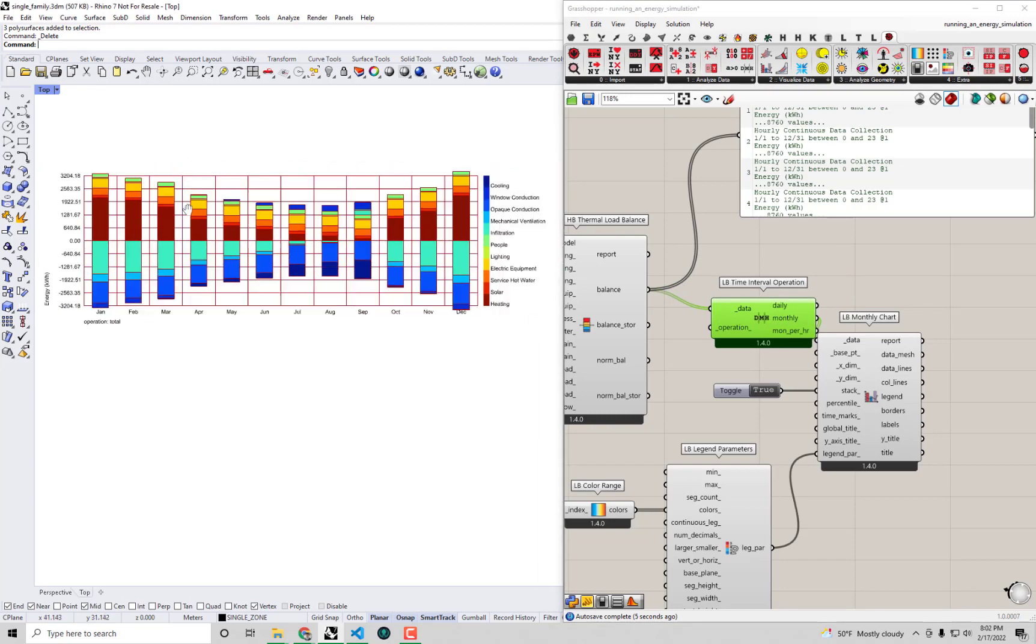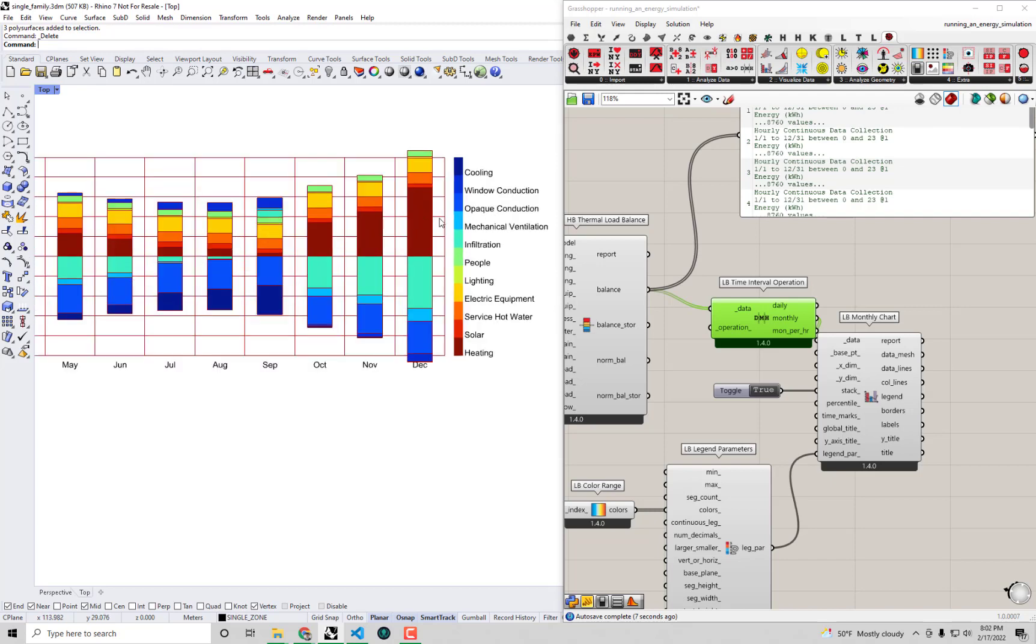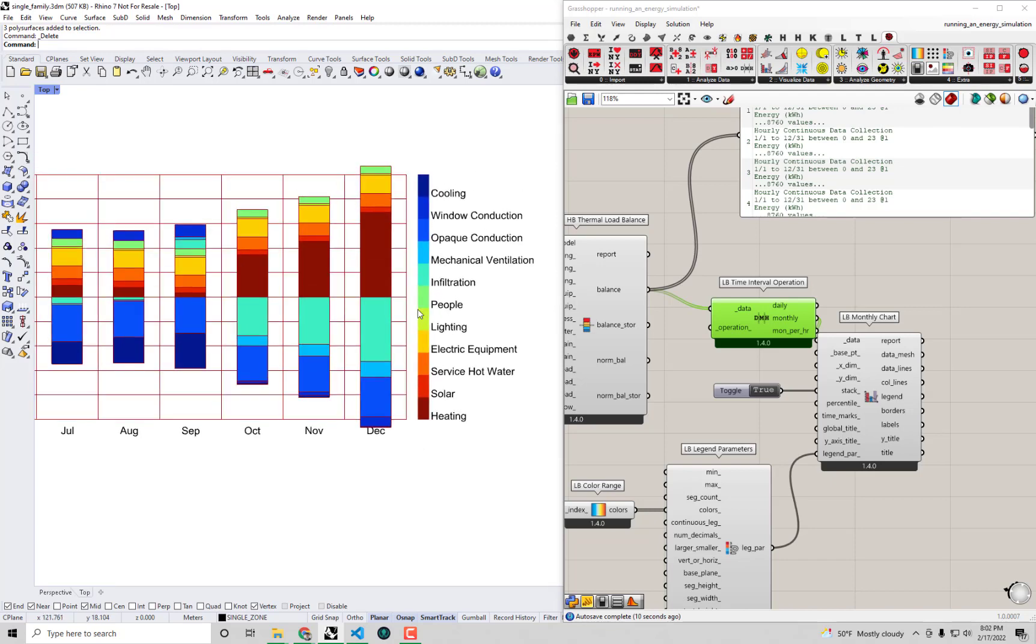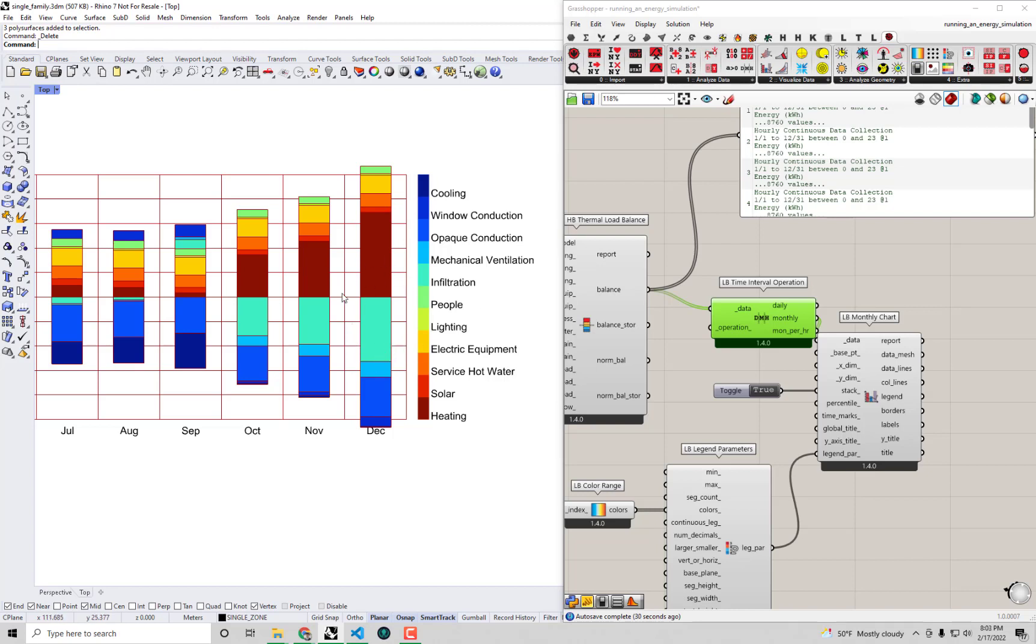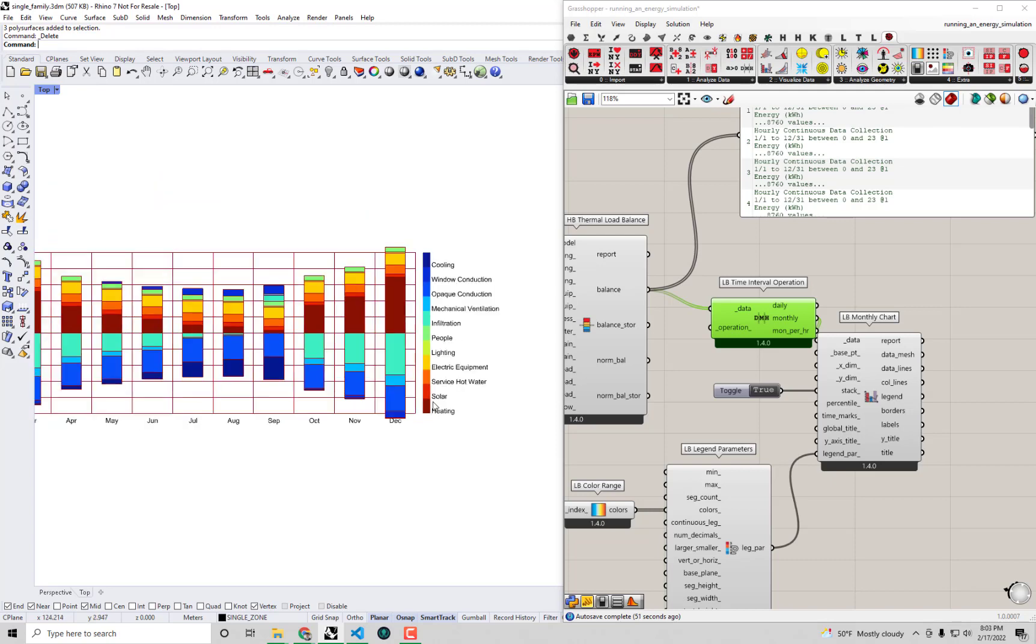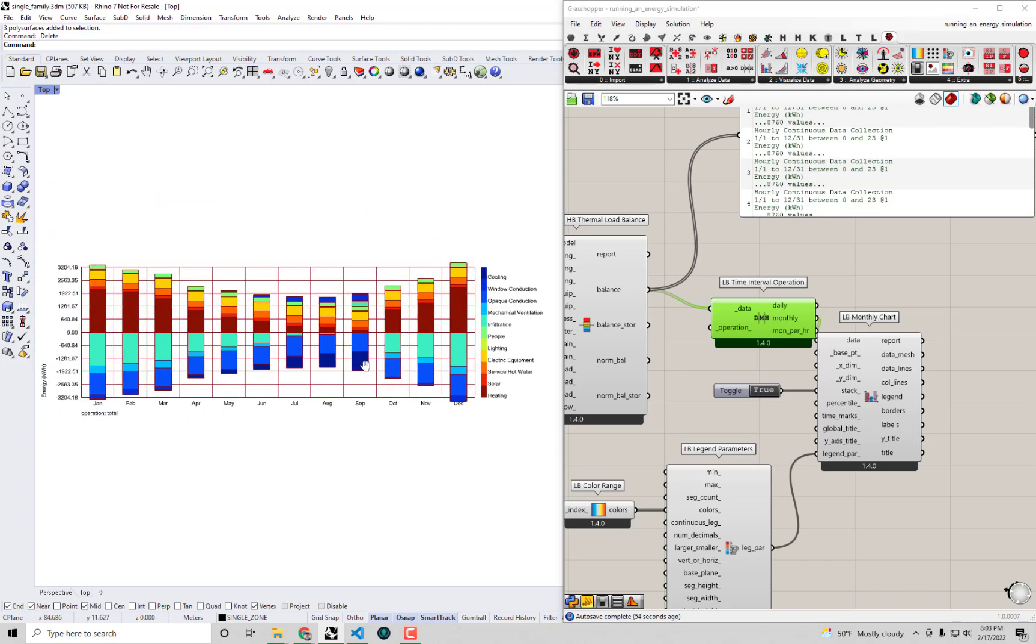So we can actually really clearly see that in this model, now that we know what all these different terms mean, if I were to pick, we realized before that the heating load was more than we expected for a house in Southern California. Usually Southern California is cooling dominated. And we can kind of understand now the reason why this single family home has such a high heating load. We can answer that question for ourselves and understand that it's actually because of the infiltration. So that's why it's so high. And we could probably also intuit, maybe the reason why the infiltration is so high is that this building has a really high surface area to volume ratio. There's a lot of surface area from which you could lose heat. And maybe that's also a big reason why our opaque conduction term is so large. So already off the bat, we have a really good strategy for what we should target if we want to improve this single family home. Especially if my mother-in-law is going to do a renovation of the single family home. If there's one thing I could really recommend to her is to really make sure that we seal up the holes and cracks in a house like this as much as possible because it has such a high surface area to volume ratio.